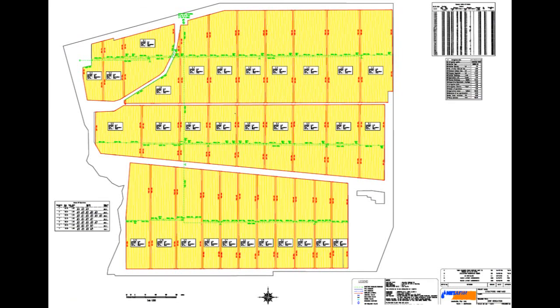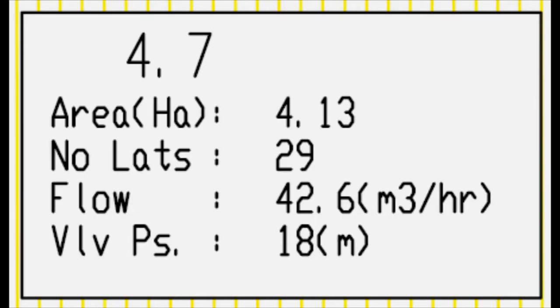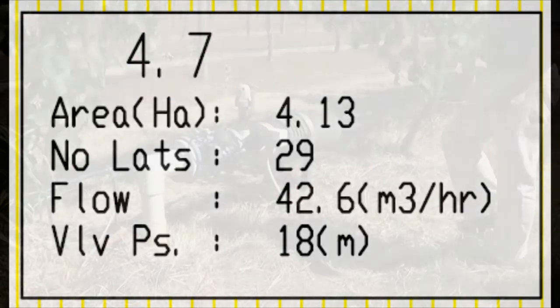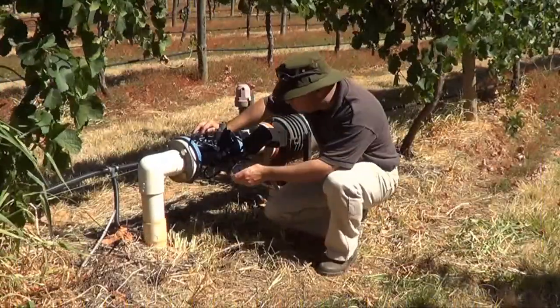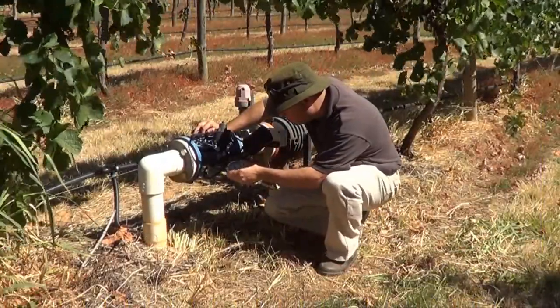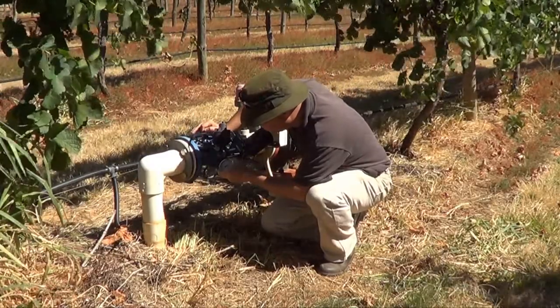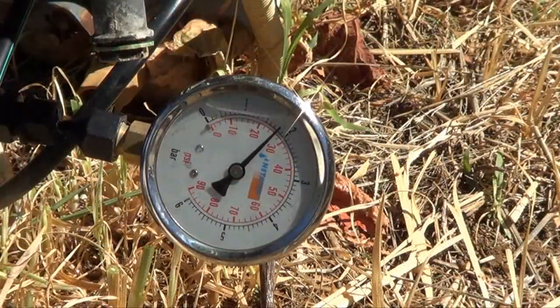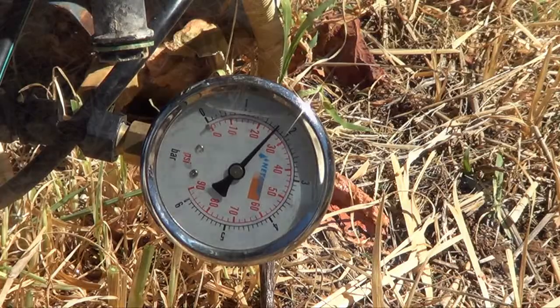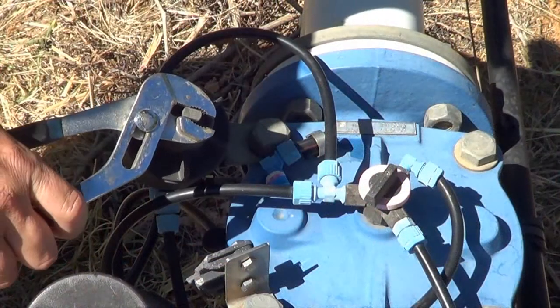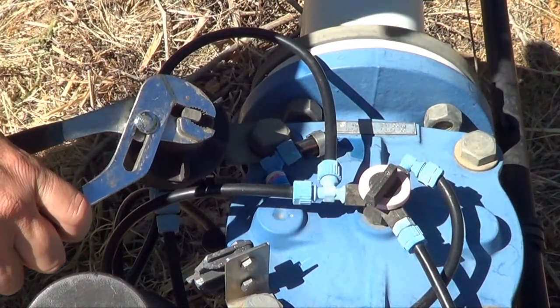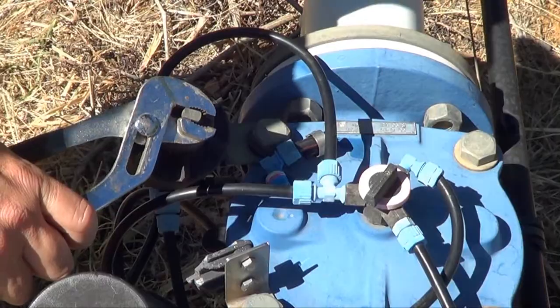It is good if you have an irrigation design to work from. Check what the valve pressure should be according to the design. In this situation it is 18 metres or 180 kPa. As we can see, this valve is running at the correct pressure. If it wasn't, we could adjust the pilot to increase or reduce the operating pressure.